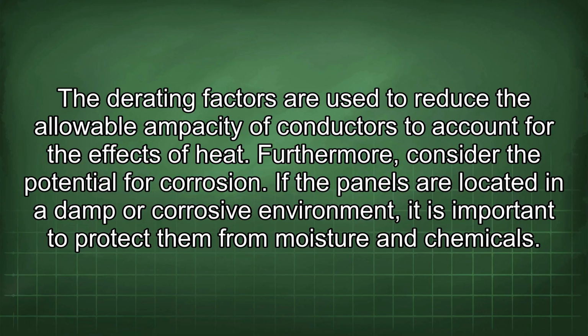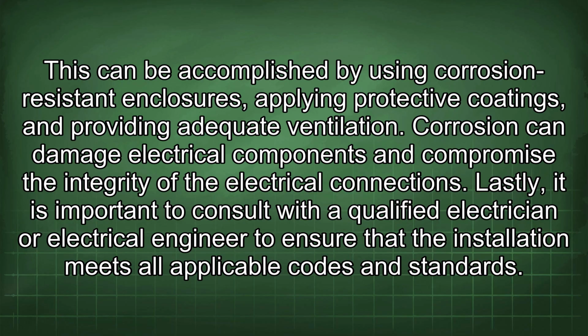Furthermore, consider the potential for corrosion. If the panels are located in a damp or corrosive environment, it is important to protect them from moisture and chemicals. This can be accomplished by using corrosion-resistant enclosures, applying protective coatings, and providing adequate ventilation. Corrosion can damage electrical components and compromise the integrity of the electrical connections.